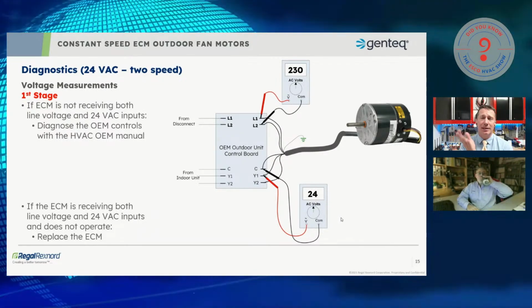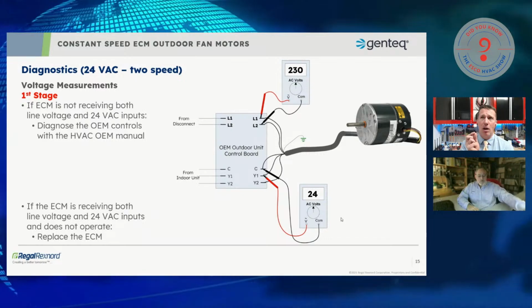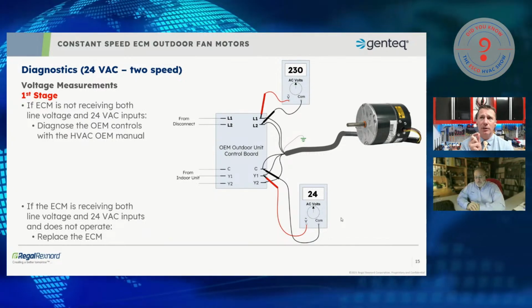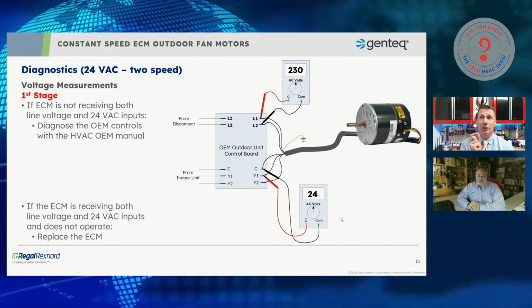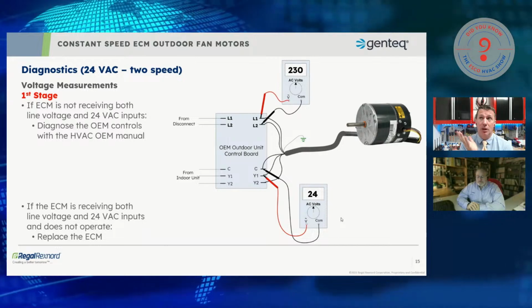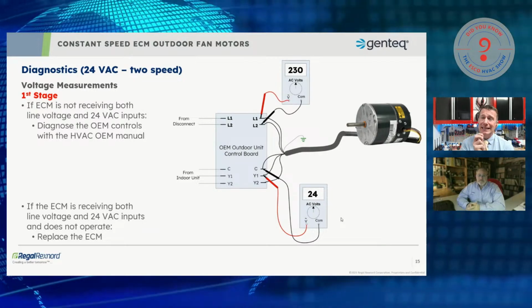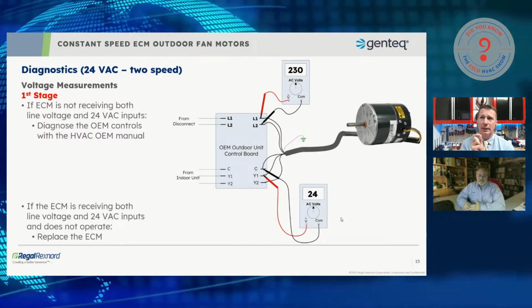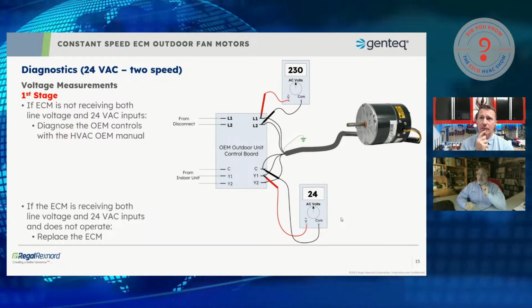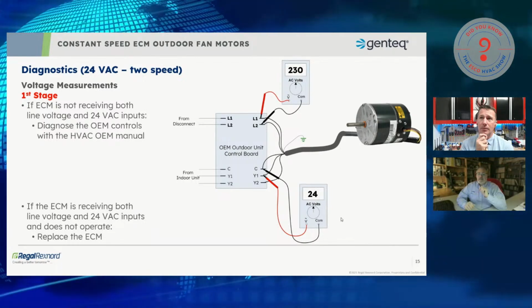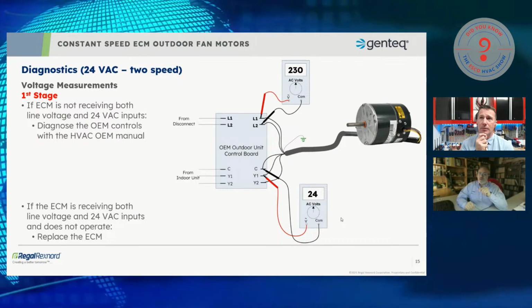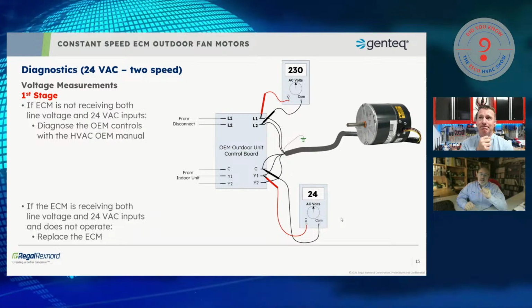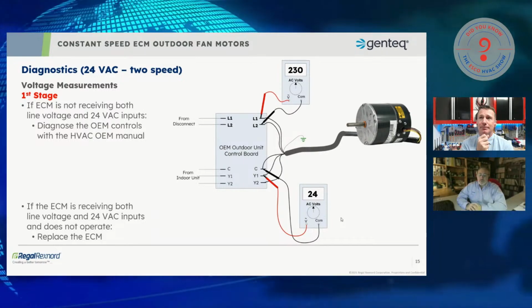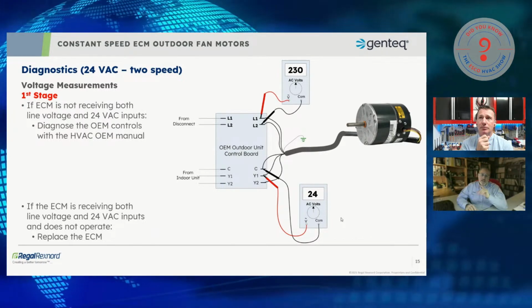Yeah, but I was wondering about that because, from the technical side, I have not myself encountered one that has lost just one low voltage side of the circuit. It's either you lose it all or you don't. So have you seen any where you've actually lost one leg? I have not on the outdoor fan, but I have on the constant torque indoor blower motor where it has the 5-speed taps. I have had technicians report to me that one tap stopped working and the other still worked.